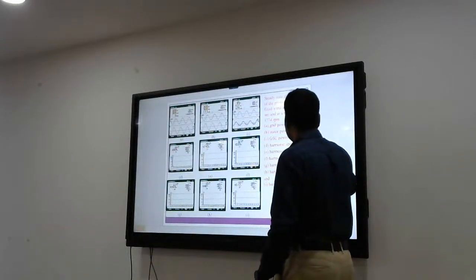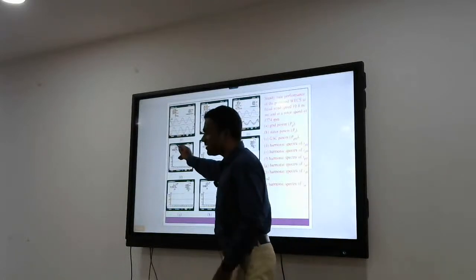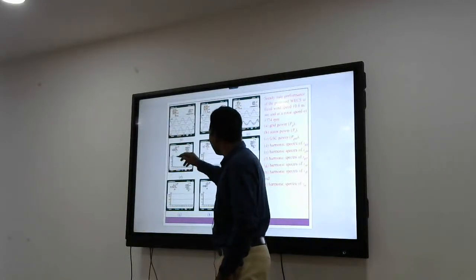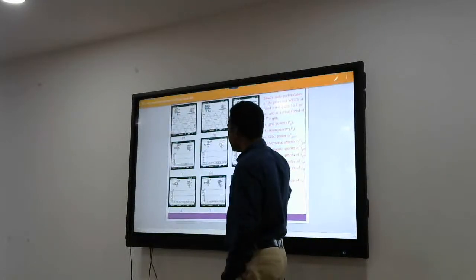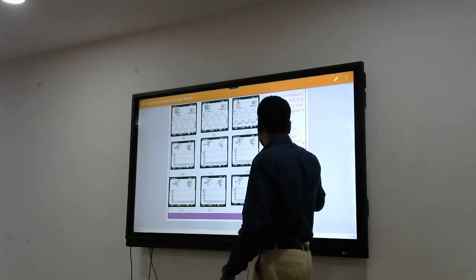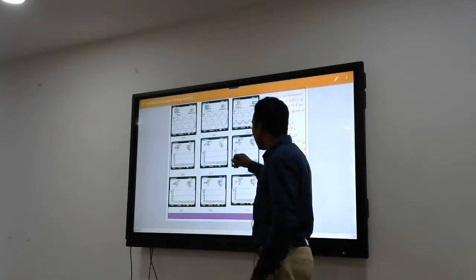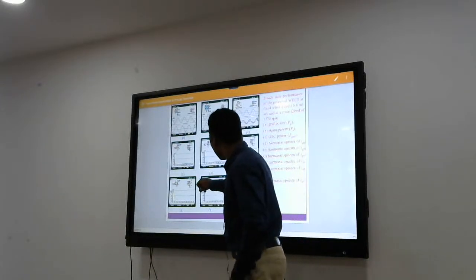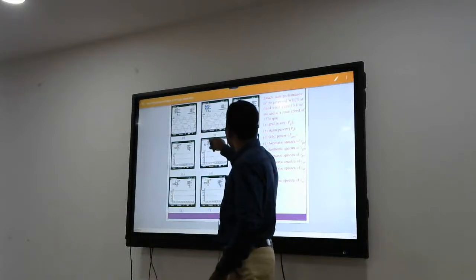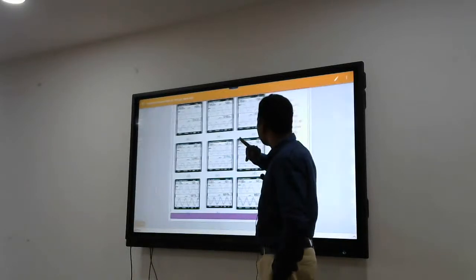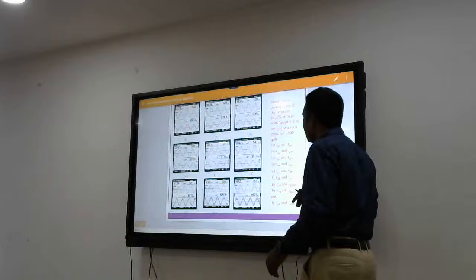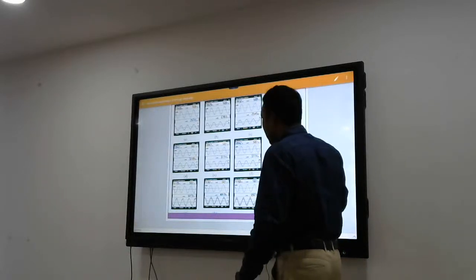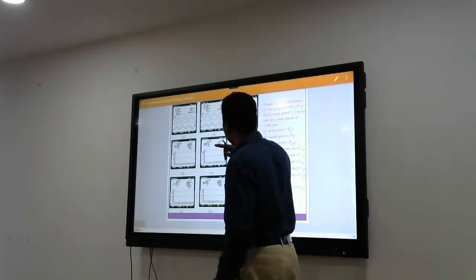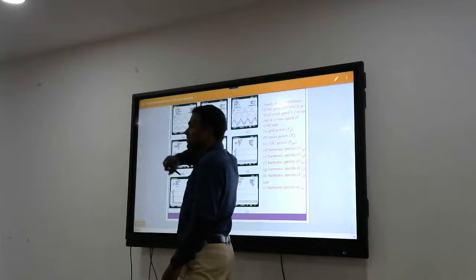This one is grid current phase A THD, this is phase B THD, this is phase C THD, and these are all stator THDs. All are less than 5%: 1.0, 1.1, 3.4, 2.6, 3.2. This is at a different wind speed, at 9.2, less wind speed. So here the power was previously 3 kilowatt, now the power is 1.73 kilowatt.